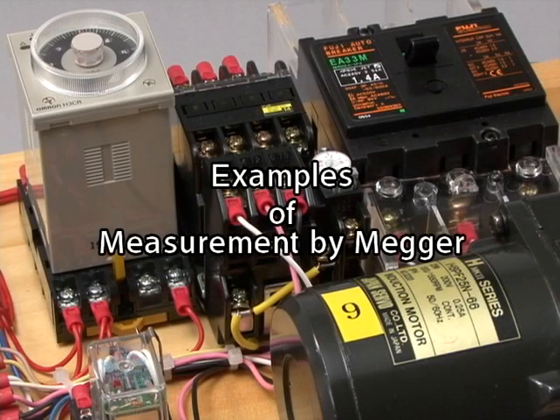The risk of electric shock increases if insulation resistance between the coil inside the motor and the case is reduced. As such, insulation resistance between the motor and the case should be measured at regular intervals. Here, let's see how to measure a motor's insulation resistance using a megger.